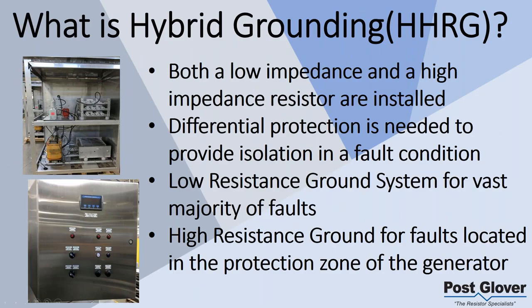This is a picture of one of our hybrid resistance grounding systems. This is a high resistance ground resistor. This is a low resistance ground. Just examples of such. You have a transformer, CTs, surge suppression, etc. We'll go over the components of it, but it's just to show you an example. Also an example of our display. For hybrid high resistance grounding, you typically would need differential protection. It's probably the cleanest and best way to provide the protection you need. We'll go into that detail more later as well.